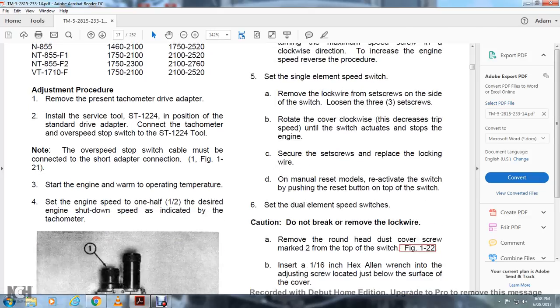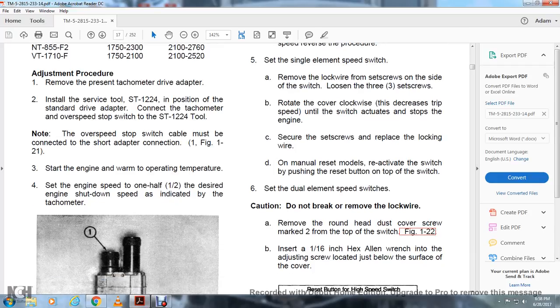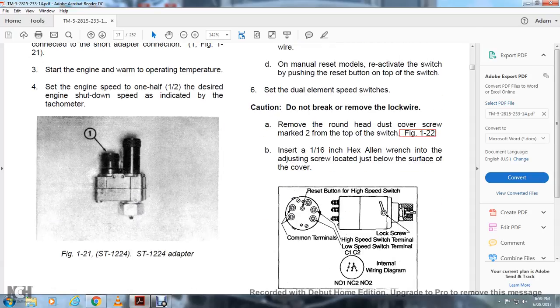Set the dual element speed switch. Caution: do not break the lock wire when removing it. Remove the round head dust cover screw marked 2 on the top of the switch, then insert a 1/16 inch hex Allen wrench into the adjusting screw located just below the surface of the cover. Reset button, high speed. For high speed switches: the common terminals, the high speed switch terminal, the low speed switch terminal, C1 and C2, internal wire diagram.